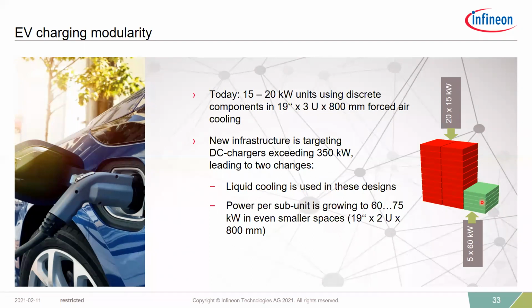This is quite important from this direction. From the design perspective, it naturally looks interesting, but what are the challenges? In the past, dissipating 300 kilowatt, even a 3% efficiency loss means roughly 3 kilowatt per 100 kilowatt, so 9 kilowatt of losses dissipated over a large area. If you try to shrink this area by roughly one-third, it means huge challenges from the power dissipation side as well. That's the reason you need to go for a high efficiency design, which will naturally eliminate those challenges.